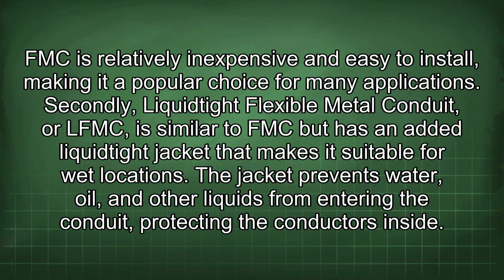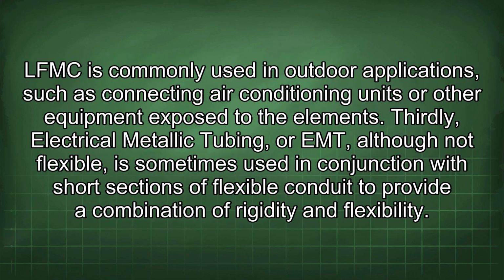Secondly, Liquidtight Flexible Metal Conduit, or LFMC, is similar to FMC but has an added liquid-tight jacket that makes it suitable for wet locations. The jacket prevents water, oil, and other liquids from entering the conduit, protecting the conductors inside. LFMC is commonly used in outdoor applications, such as connecting air conditioning units or other equipment exposed to the elements.